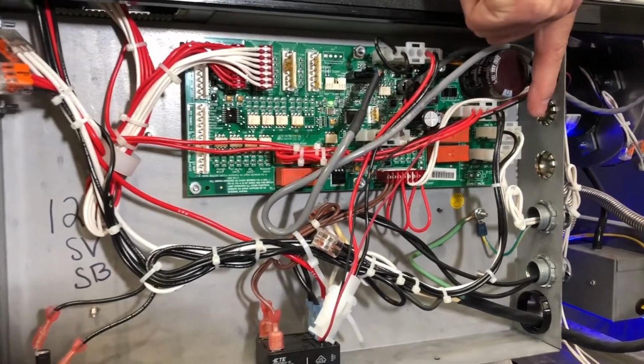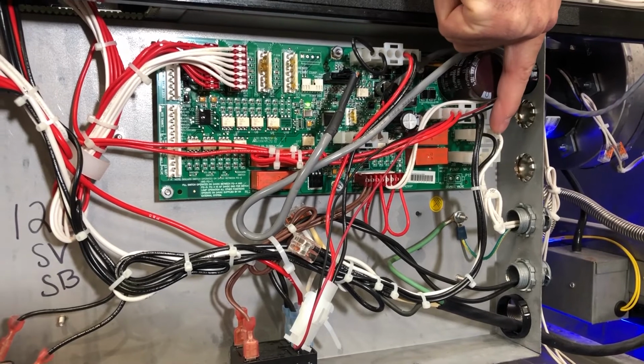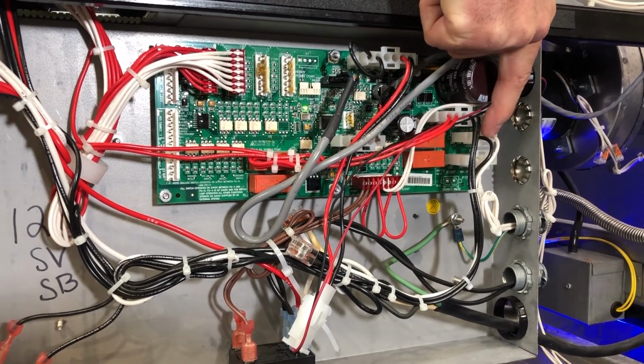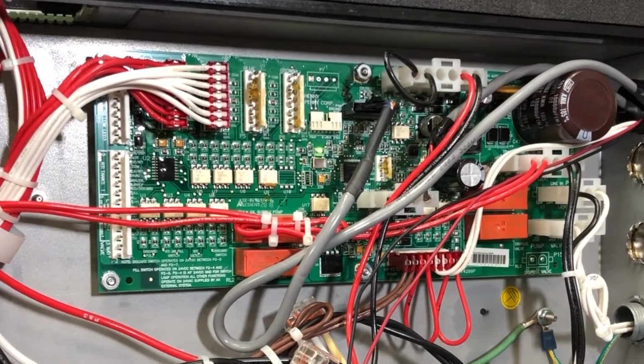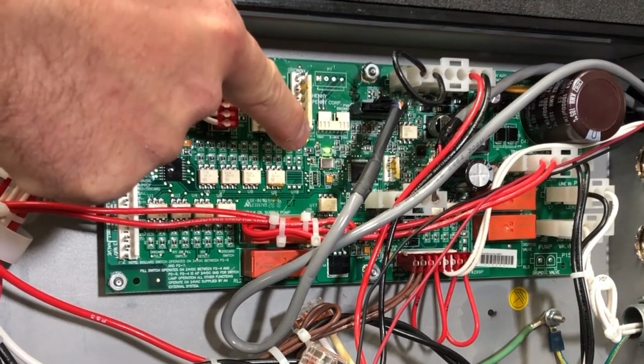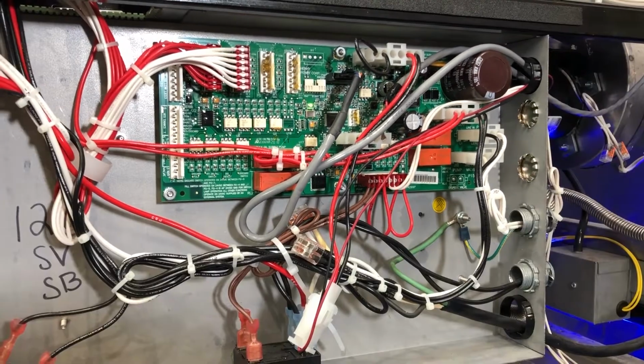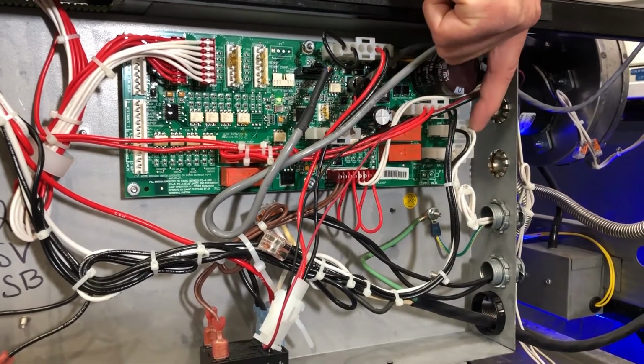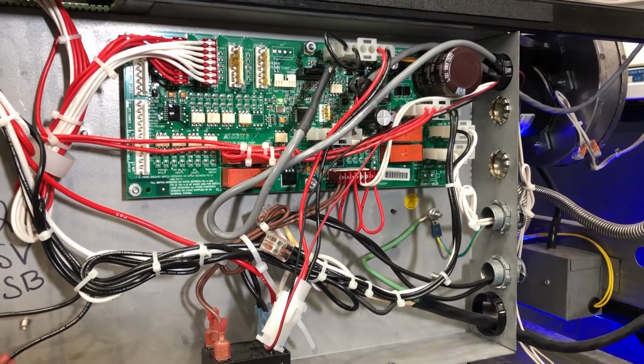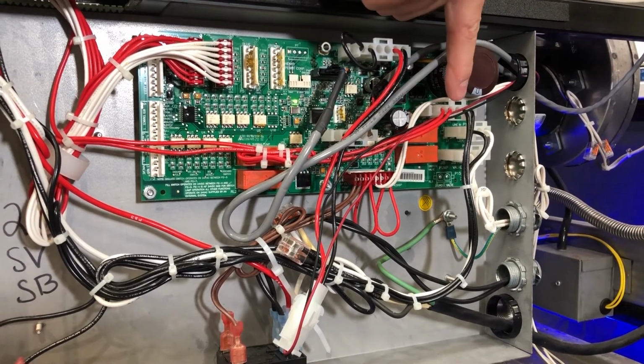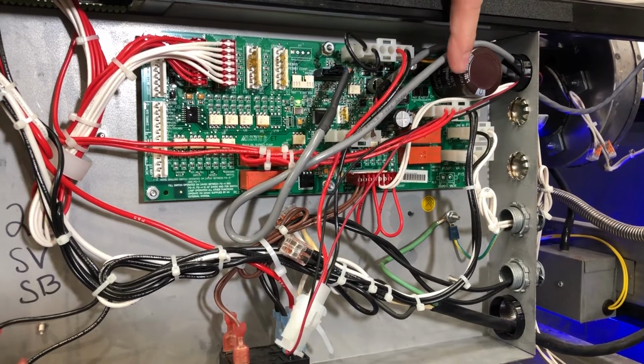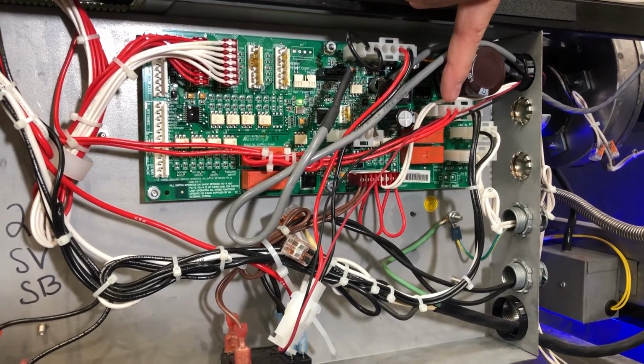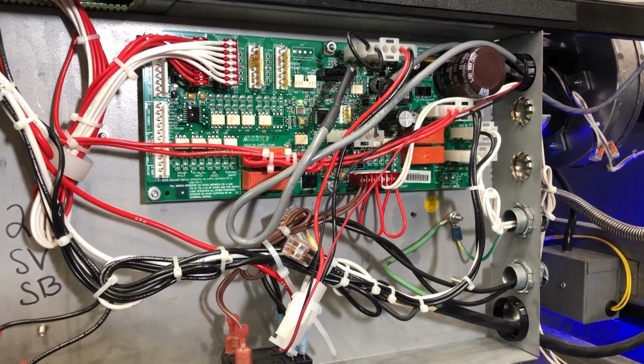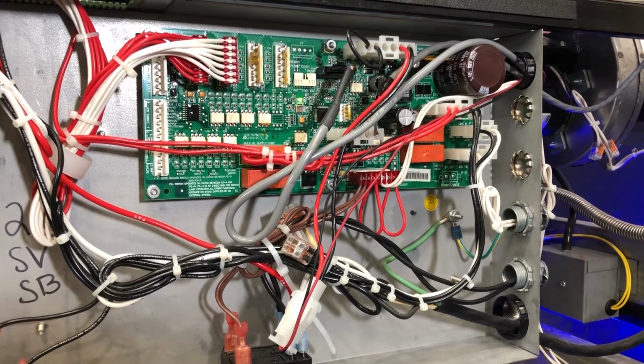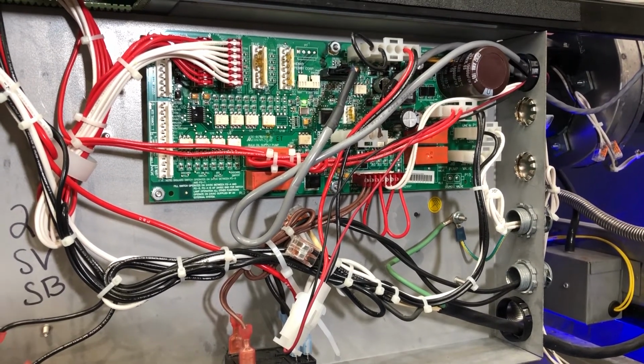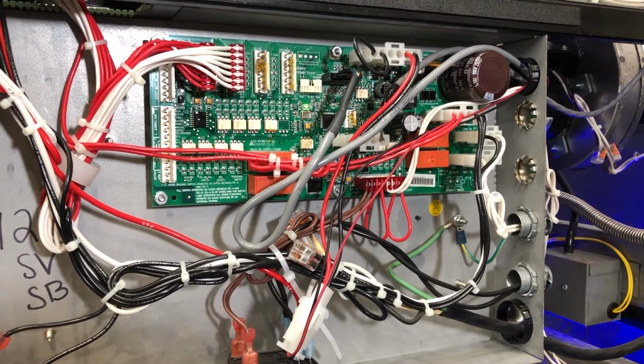This fuse protects the AIF board coming into our P12 connector, our line voltage input connector. If we see this LED light on the board not lit up, there's a good chance we don't have line voltage coming into our board. We can then check our transformer plug and make sure we have 18 volts AC on our two red wires coming into the board, which powers up our AIF board.